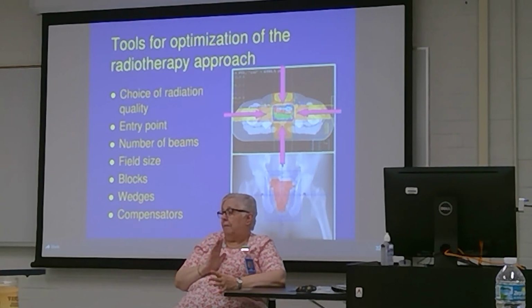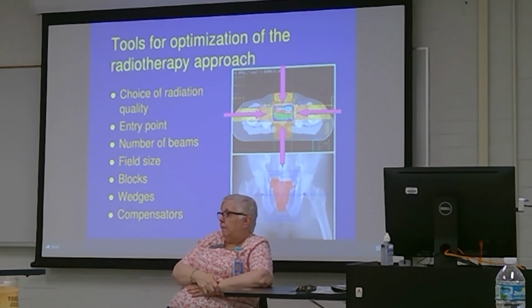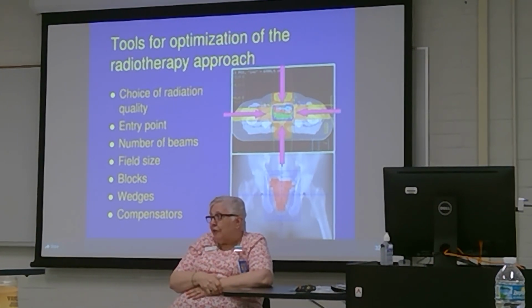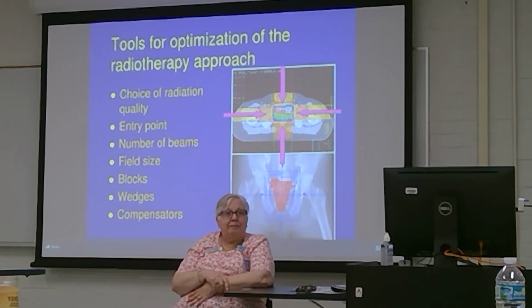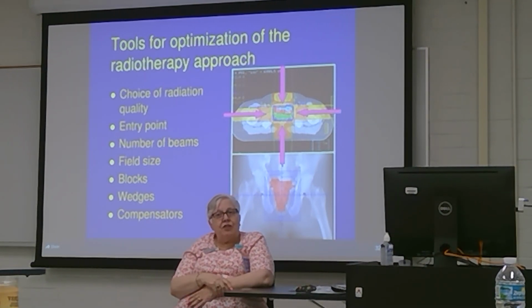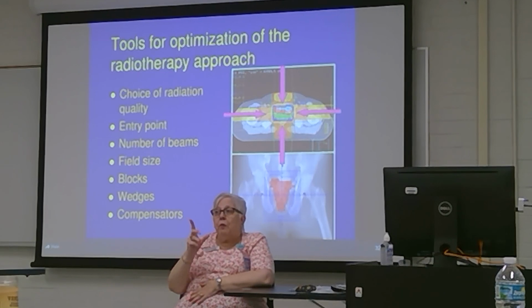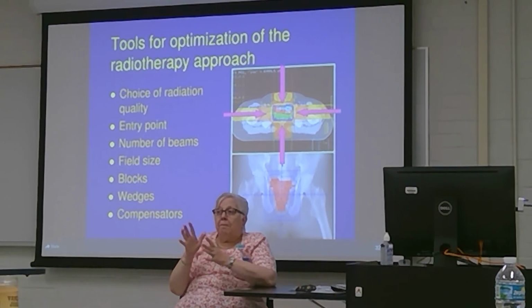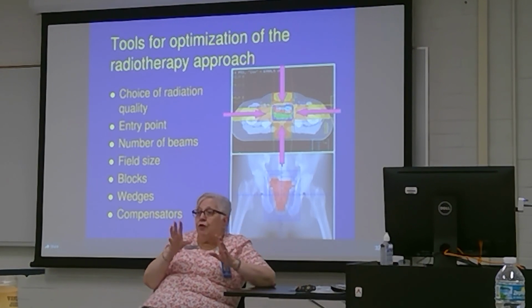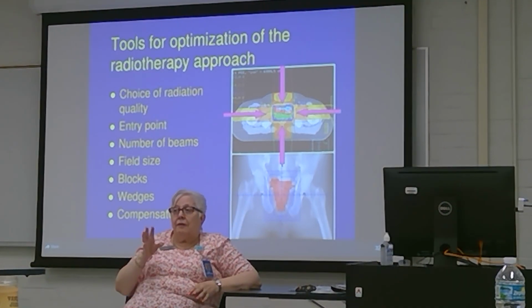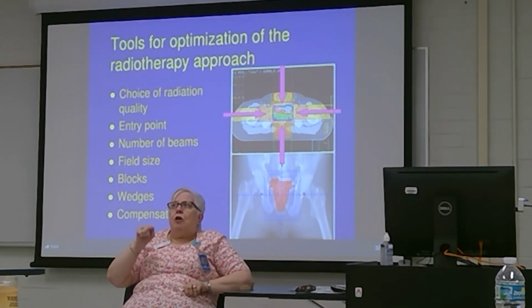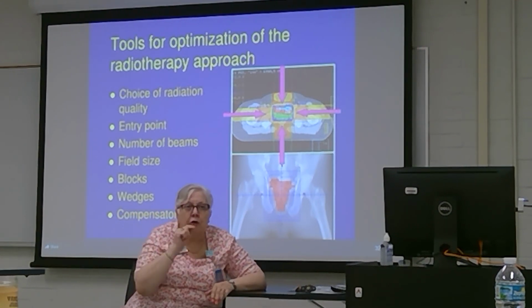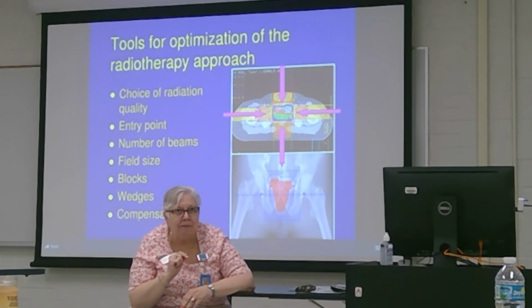Now, does the AP one line up exactly with the sagittal one? Yes, at isocenter. I never noticed. Yeah, at isocenter. So, that's one way to do it without a light beam. But again, you should not rely for setup on your cone beam CT.